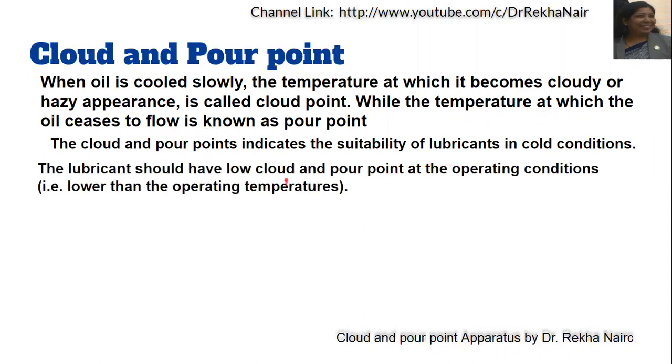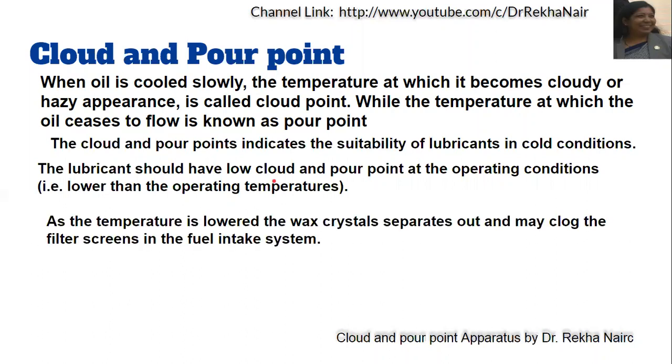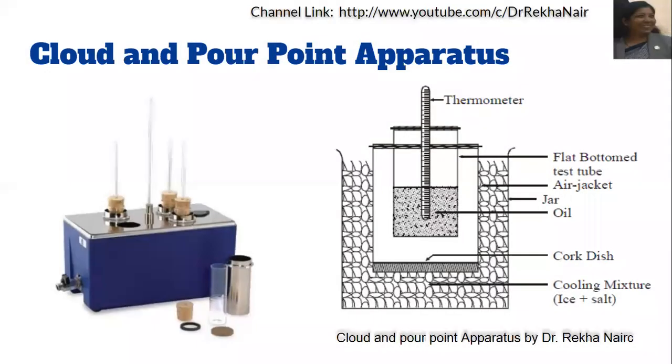The lubricant should have a lower cloud point and pour point than the operating conditions. Or we can say that the operating temperature should always be higher than the cloud point and pour point. As the temperature is lowered, wax crystals separate out and may clog the filter screens in the fuel intake system. A high pour point may jam the machines.